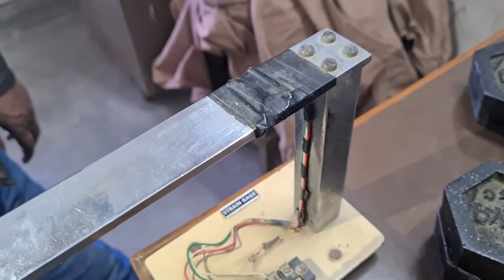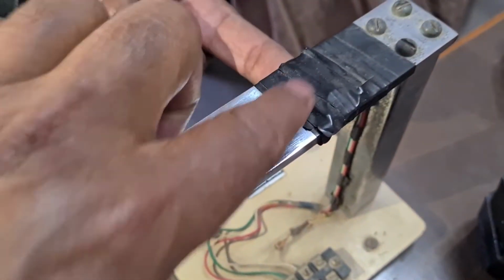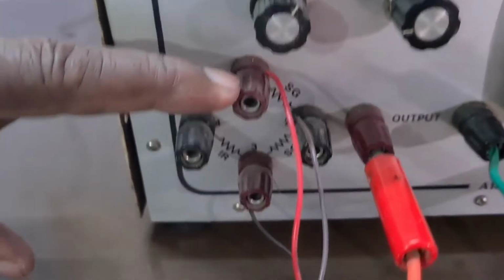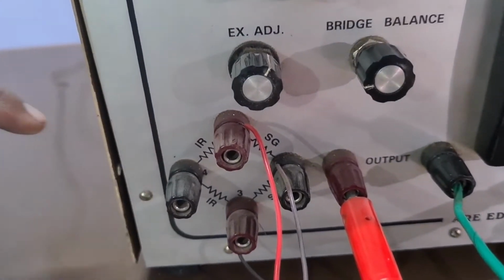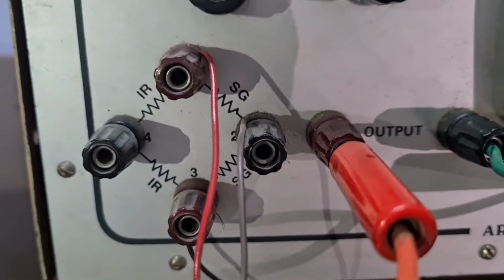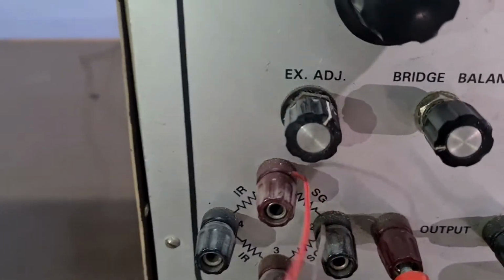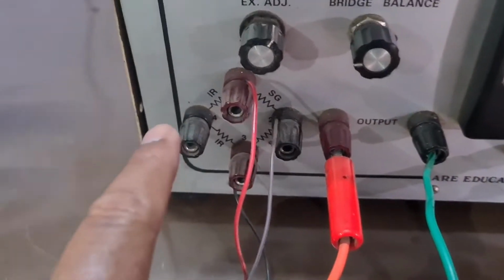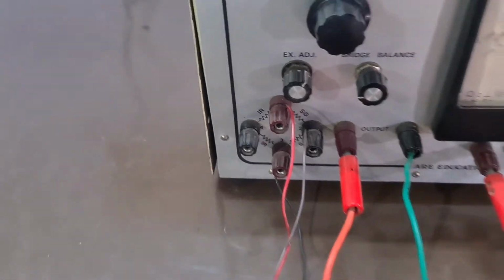Here two strain gauges are mounted on the top side and two on the bottom side. One on the top side, one on the bottom side, and then their connection is given here, a common point. Then they have given it in a Wheatstone bridge. You see point one, then second point, third point and fourth point. This connection is given as a half bridge. One connection is not there, it is open, so this is a half bridge.